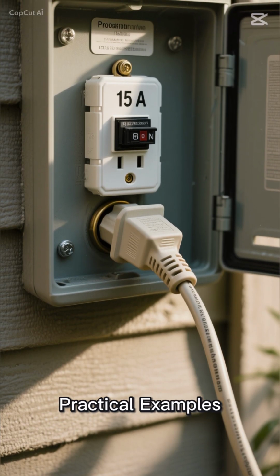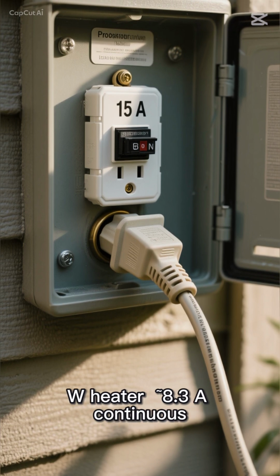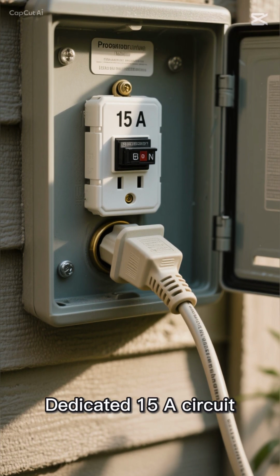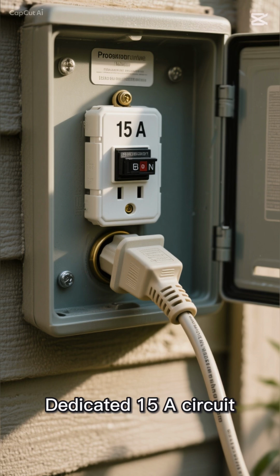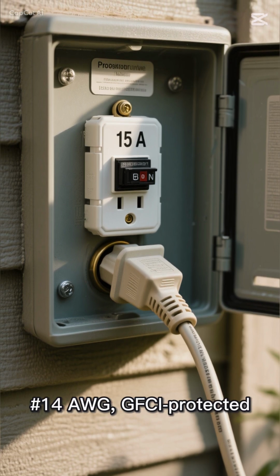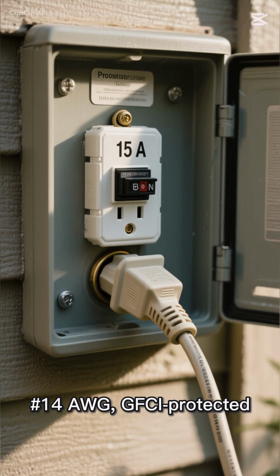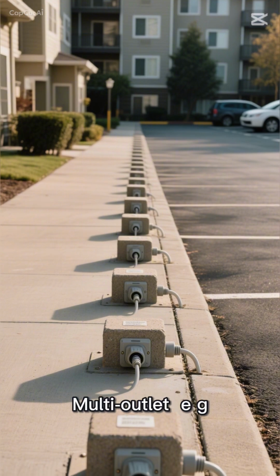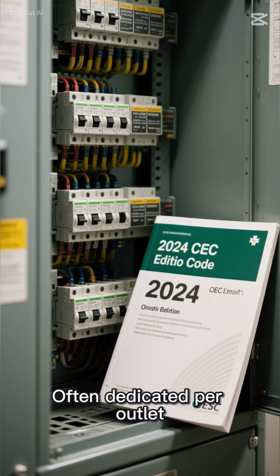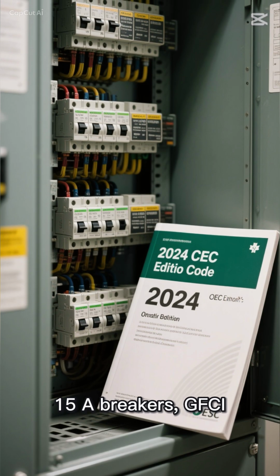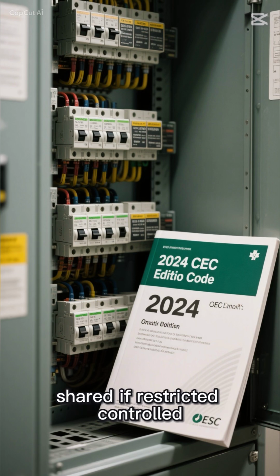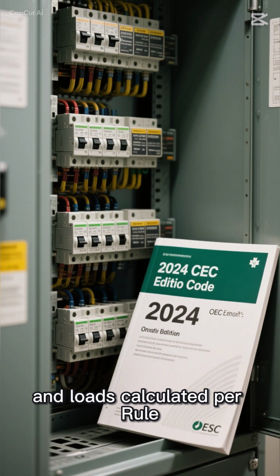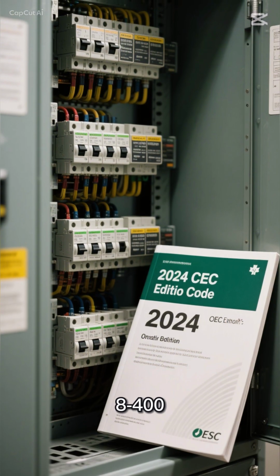Practical examples: single 1000W heater, 8.3A continuous, dedicated 15A circuit, 15A breaker, 14 AWG, GFCI protected. Multi-outlet, e.g. apartment parking: often dedicated per outlet, 15A breakers, GFCI. Shared if restricted, timer controlled, and loads calculated per Rule 8-400.